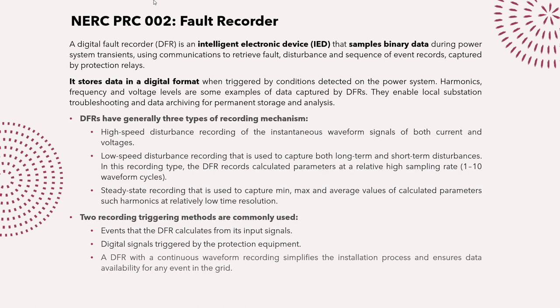A triggering criteria must be defined for storing data. The DFR can trigger based on the type of event, type of parameter, or threshold values — for example, if current rises above or falls below a set quantity, or voltage drops below a threshold. Depending on these triggering criteria, the fault recorder will detect and record events. It can be part of the protection system or a standalone system located in a substation or generating plant.